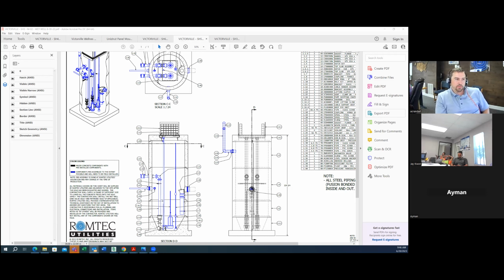What we'll do before startup is I'll check in with you after installation - you've already got the control panel, sounds like that can be installed pretty quickly. Once the conduits are set through the wet well, I'll send you a checklist and ask for some photos. My engineers will review it and come up with a punch list of things that might need to be completed before startup, but we'll get you on the schedule as quickly as we can.